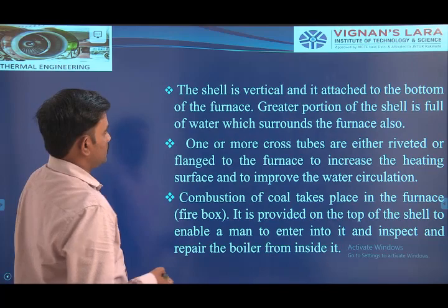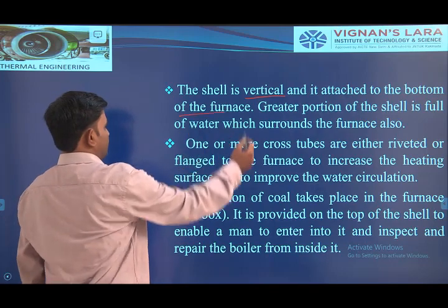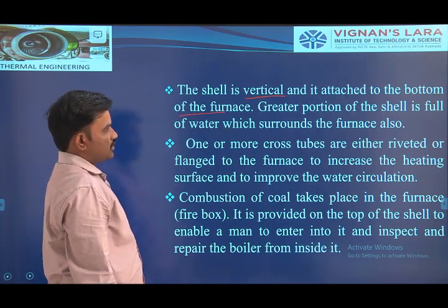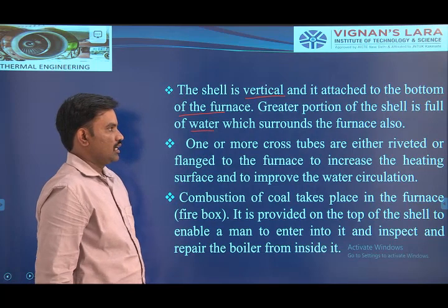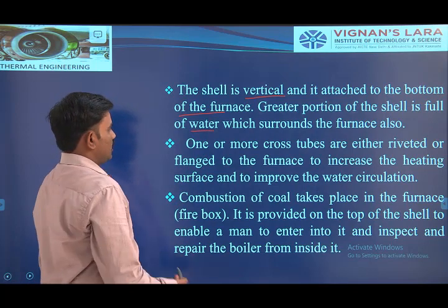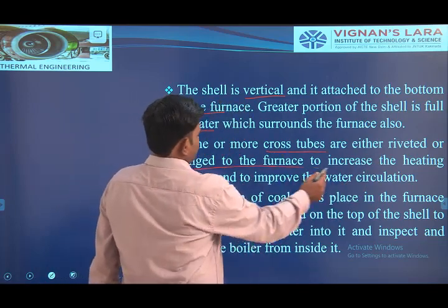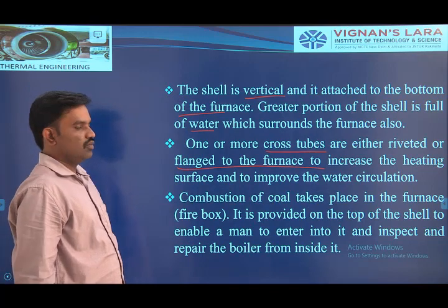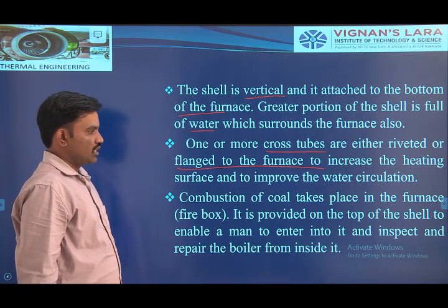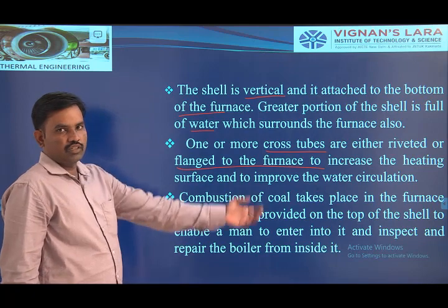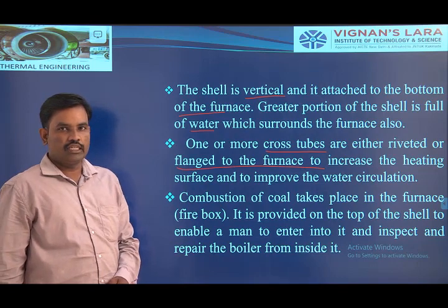The shell of the boiler is vertical and attached to the bottom of the furnace. The greater part of the shell is full of water which surrounds the furnace. Inside the shell we are placing the water, and the furnace releases the hot flue gases. One or more cross tubes are either riveted or flanged into the furnace to increase the heat transfer surface and improve the water circulation. With the help of burning fuel, we are generating heat energy, which is supplied to the feed water.